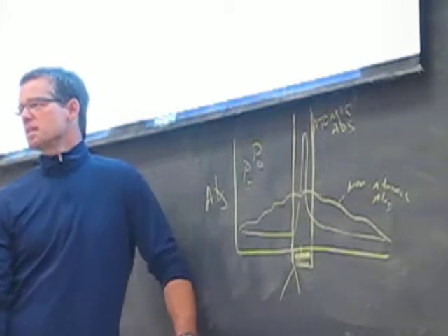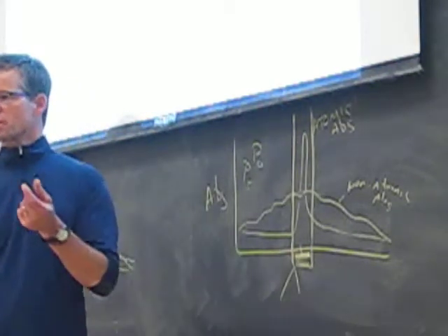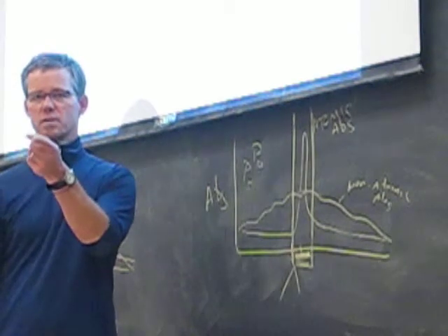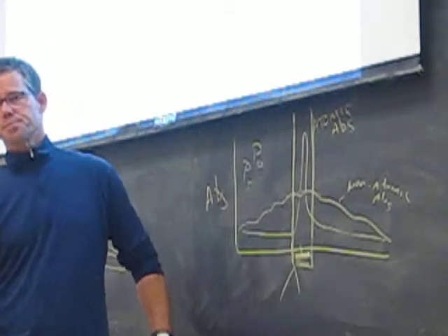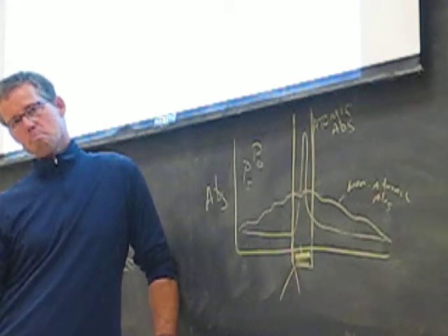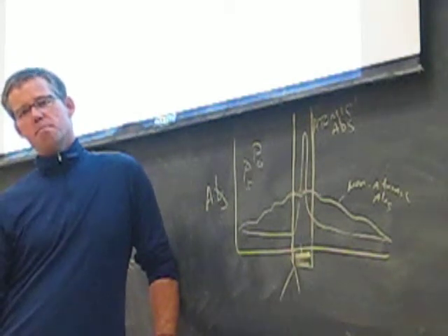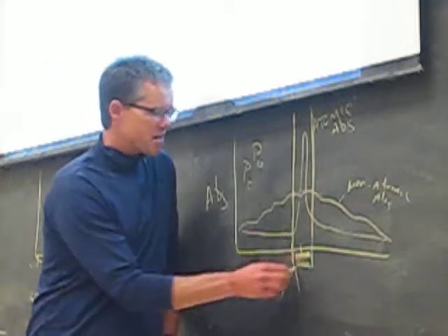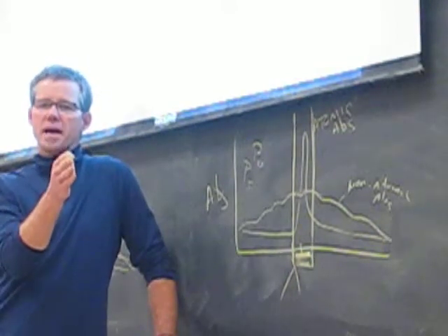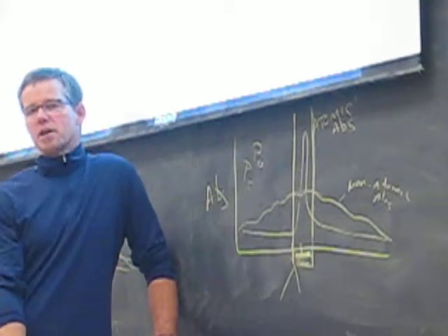6 or 7 and 324.9, and you're measuring all the absorbance that's occurring within that bandwidth of wavelength. Since the peaks are theoretically at least a Gaussian curve, you could measure the absorbance at like 1 or 2 standard deviations away from the center. If you could measure that finely, at intervals of 0.01 or 0.001 nanometers, you might be able to do that. But monochromators aren't that effective.